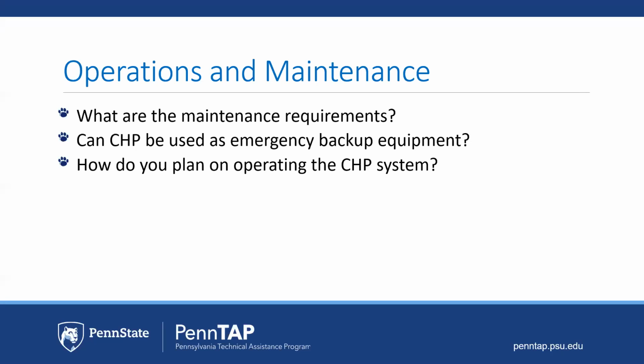The way we think about it is the engine, or the CHP system we have, we'd like to run as fully as possible, for a few reasons. The efficiency of the system is better when run continuously, and we want to recoup the advantages of the system since we have a need for the electricity, plus the thermal requirements—steam, chilled water, and hot water. So we intend to operate the system continuously at full capacity, because that's how it was built and designed.